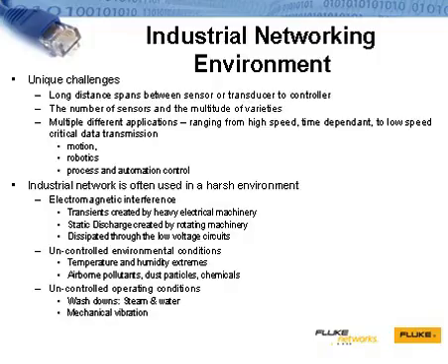So can you give us a few examples of the problems a harsh environment creates for the networks? Sure. For example, we have seen at specific customer sites problems in a variety of different environments. We've seen water intrusion from shift change washdowns. We've seen extreme freezing temperatures in a frozen food plant affecting components over just a short period of time.